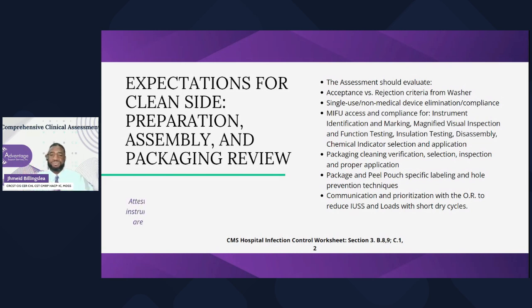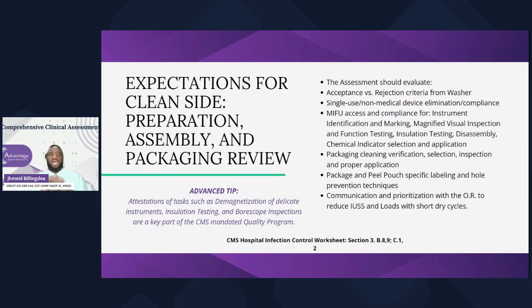So an advanced tip is attestations of tasks such as demagnetization of delicate instruments, insulation testing, and borescope inspections are a key part of a CMS mandated quality program. And we're going to talk about that a little bit later on, but these are the things that are in that quality program. And that's how you can use your count sheet and your instrument tracking system to ensure that your team is doing all the things that, one, they're being asked to do by accreditation standards, but also the things that lead to better products and patient care.